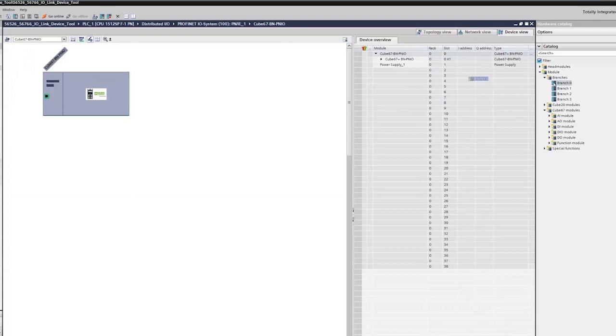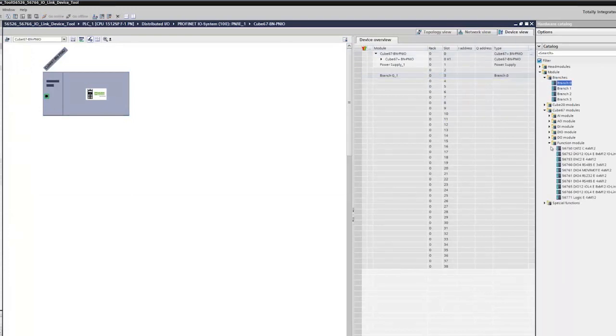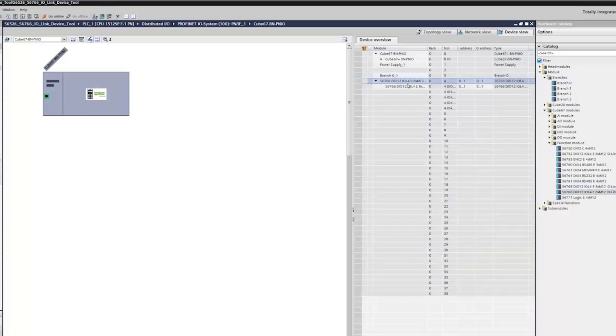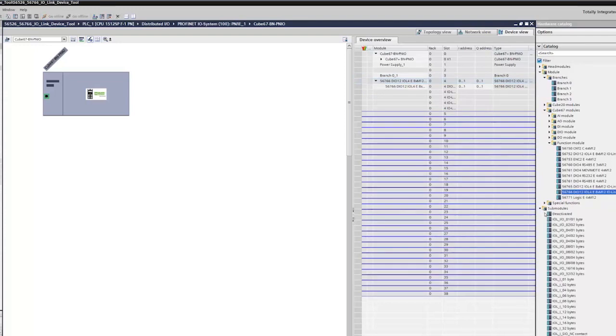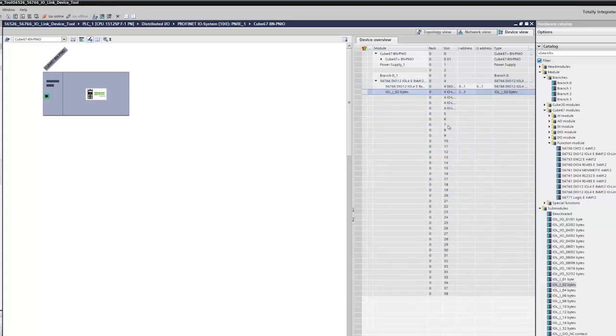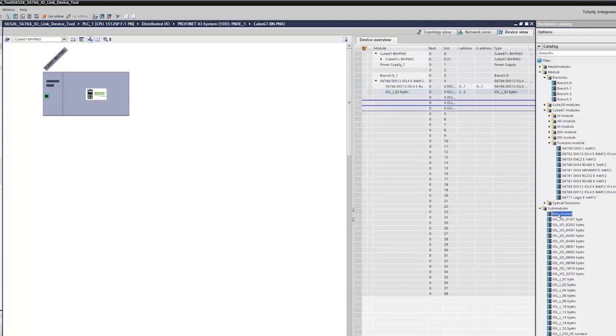Insert branch 0. Add the IO-Link master module to branch 0. Configure the first IO-Link master port as an input with two bytes. Deactivate the other three ports.